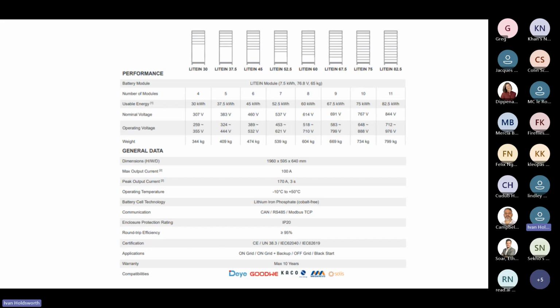It's always important to make sure that the inverter that you're connecting to is on the compatible list, and that your number of modules is within the recommended number of modules, because if you have too few or too many, that battery voltage will be outside the operating voltage of the inverter. And here we can see the dimensions as well.